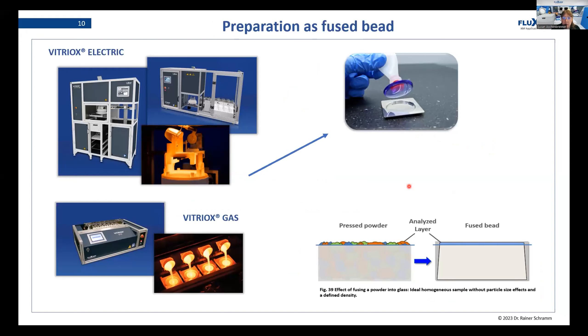What can we do to get better results? We can prepare our sample as a fused bead. To do this, there are different possibilities: an electric muffle furnace, an automatic fusion machine, or a gas-driven automatic fusion machine. You can also fuse by hand, though this is not really common anymore. The aim is always the same — to get a fused bead in which all of your components are oxidized, so they are all on the same level and will always fit into the calibration.